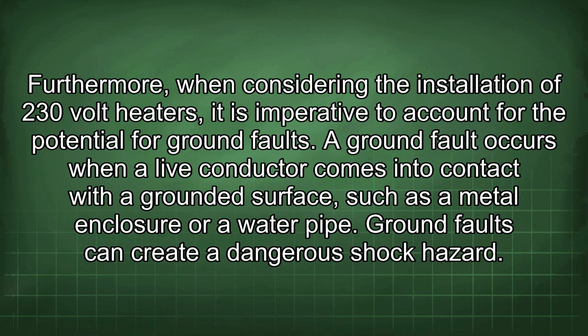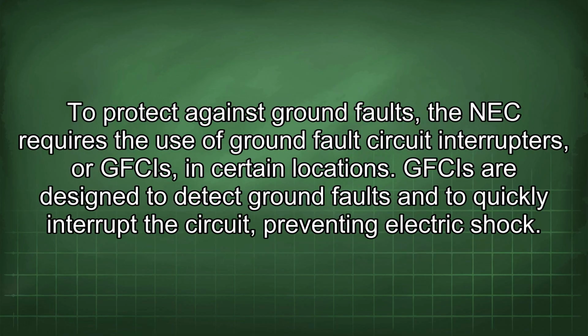A ground fault occurs when a live conductor comes into contact with a grounded surface, such as a metal enclosure or a water pipe. Ground faults can create a dangerous shock hazard. To protect against ground faults, the NEC requires the use of ground fault circuit interrupters, or GFCIs, in certain locations. GFCIs are designed to detect ground faults and to quickly interrupt the circuit, preventing electric shock.